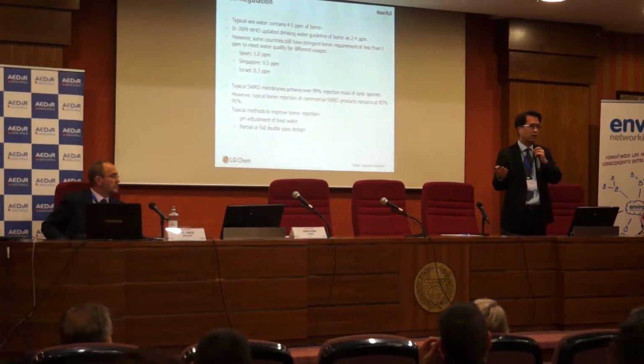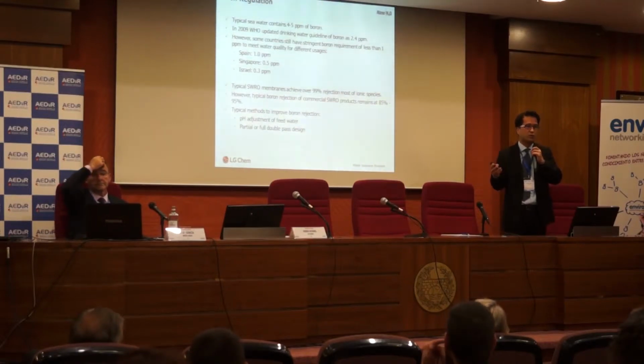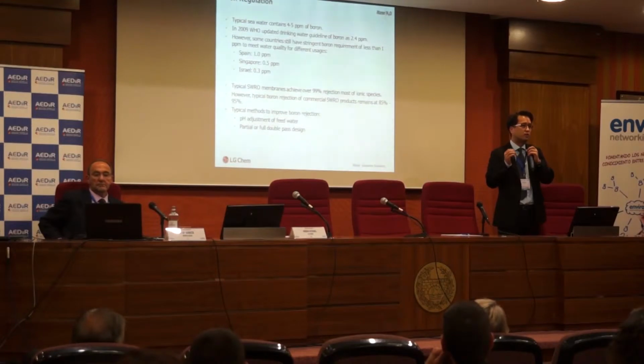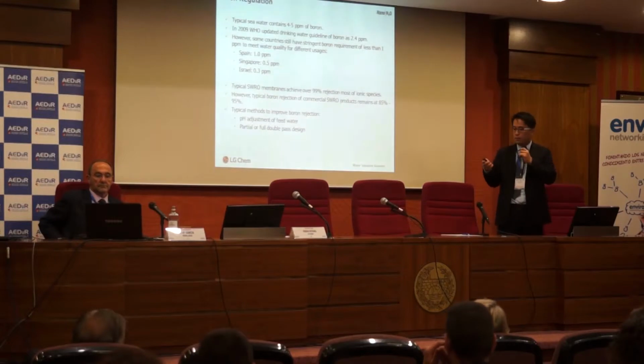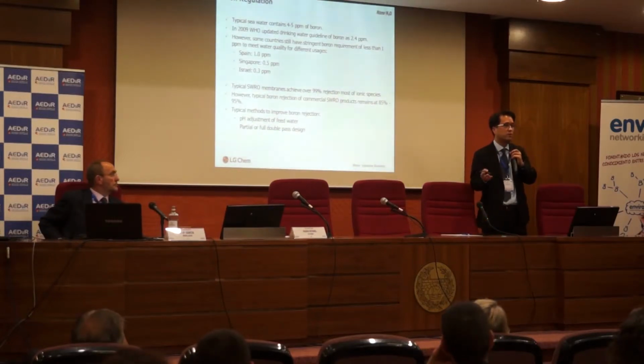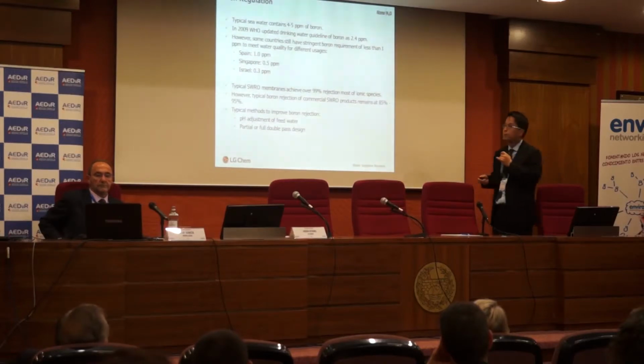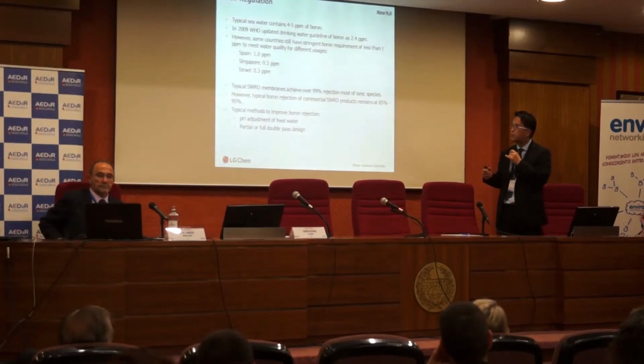In certain areas outside of Spain, for example in Singapore, the project requires 0.5 ppm of boron, and even in Israel, they have a more stringent boron requirement of 0.3 ppm. So in those areas, for some projects, boron is the limiting factor for the system design. There are several other parameters you have to meet for the drinking water guideline or some application guidelines, but compared to these cases, TDS or chloride will probably be easier to meet. So in many projects in this region, boron is the limiting factor for your system design. A typical SWRO membrane has pretty good removal of ionic species like sodium chloride, more than 99% rejection.